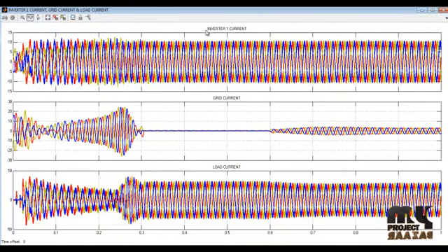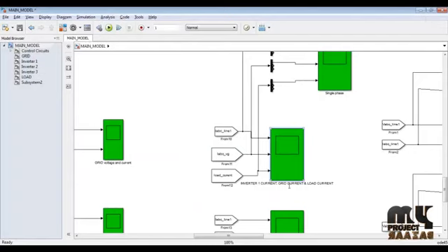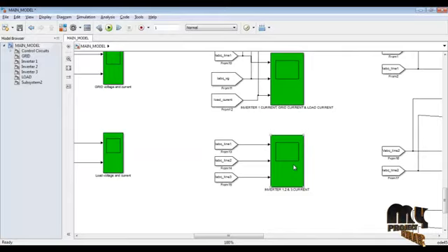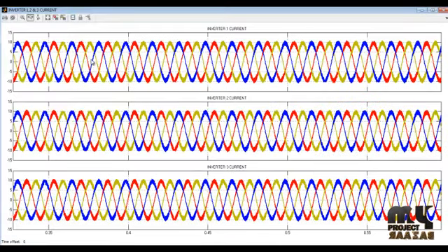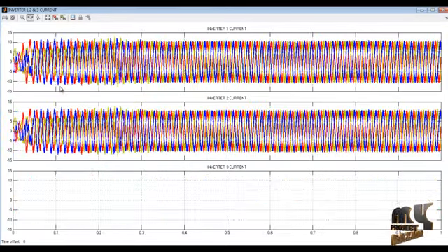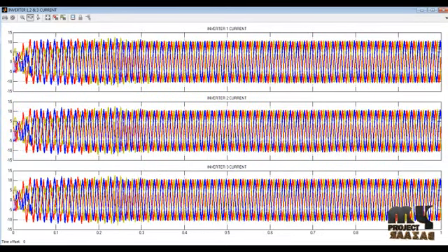We are using three inverters. This is an inverter 1 current, this is the grid current, and this is the load current. So these are different categories for the load, the inverter and the grid. This is the inverter 1, 2 and 3 current. The inverter current reaches a maximum range of 10 amperes.